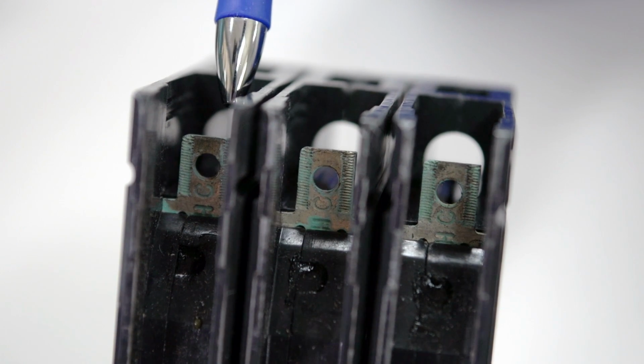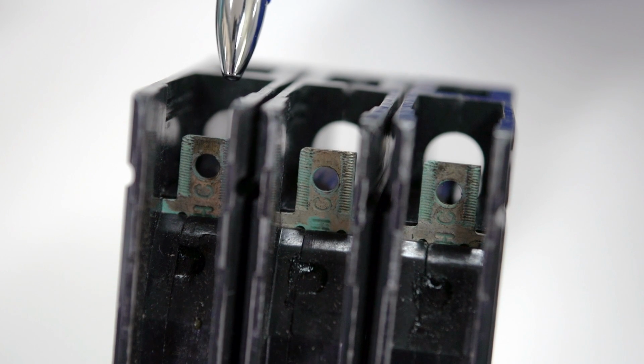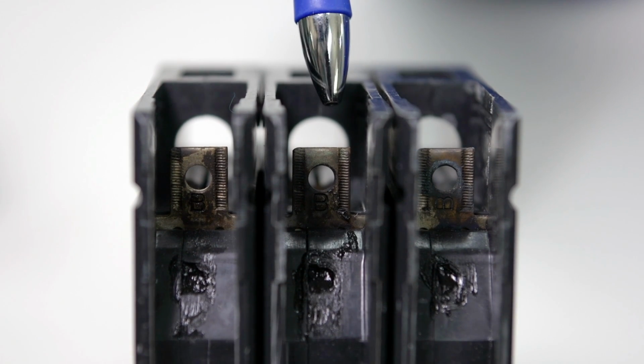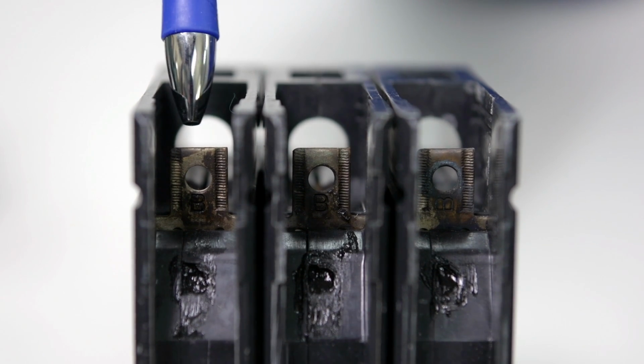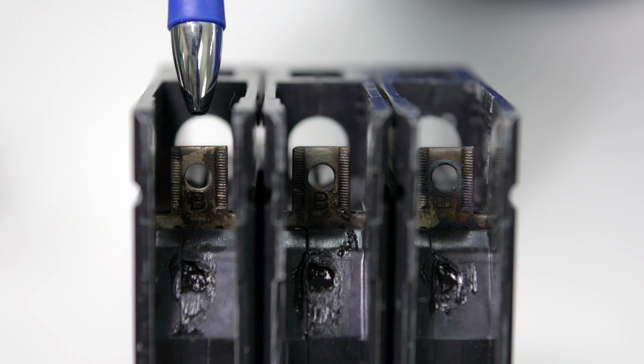If you have this on the outside, you don't know what you have on the inside. This will inhibit current, it will influence current. And this one has seen some serious heat within its life. It has, in all likelihood, seen a short that's affected its ability to perform to the required standards.